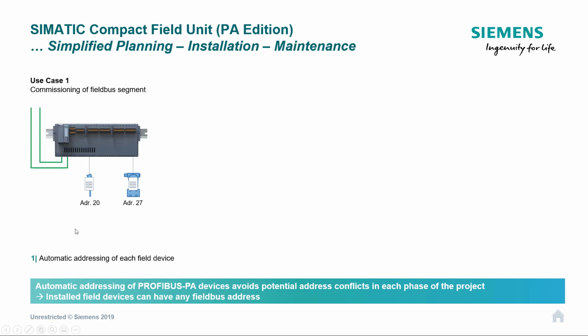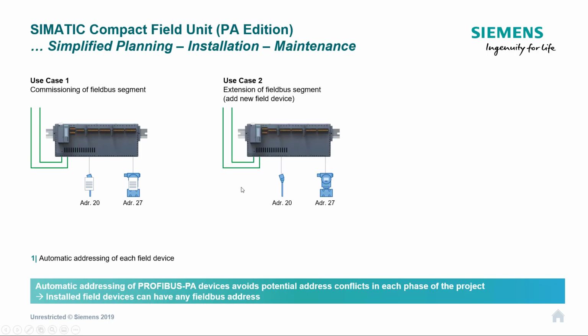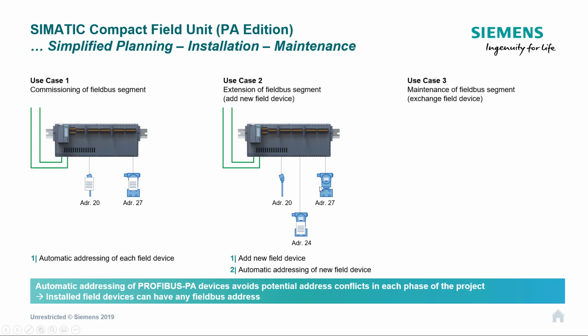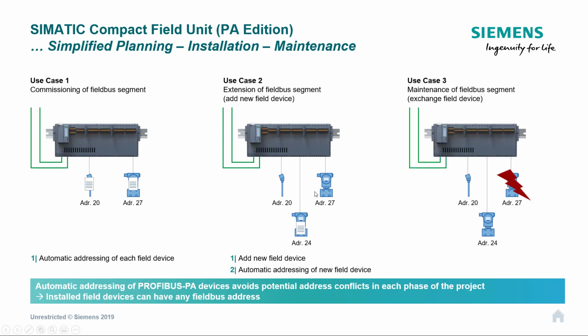It speeds up commissioning because I no longer have to get a network drawing out. As long as I've plugged it into the right hole, it's going to have the right address. If I need to add a device at a later date, as long as I have a spare port on my Compact Field Unit, as soon as I add my device, first thing it does is automatically address. So the last case is probably the most awkward, is when you've got a failed instrument.